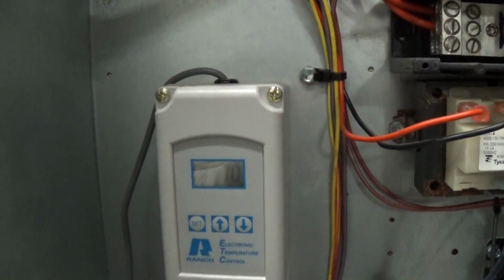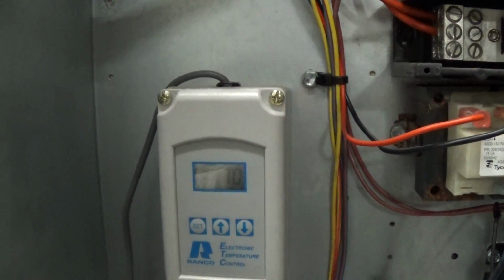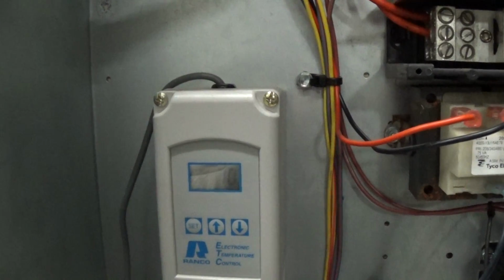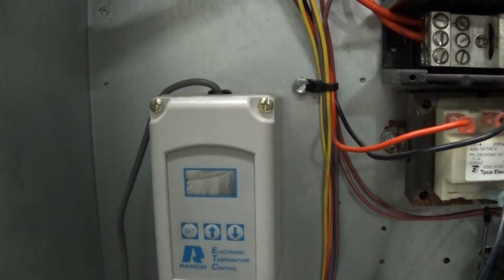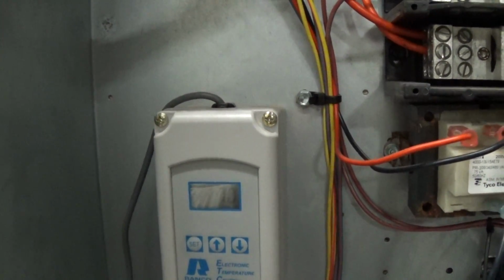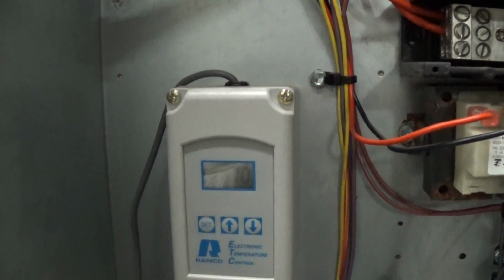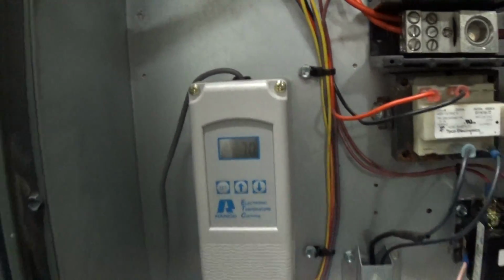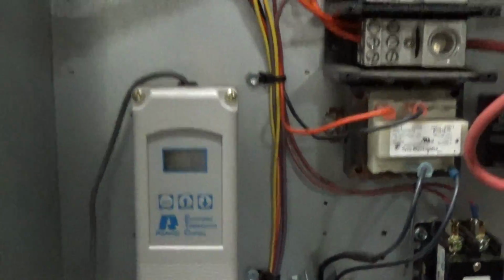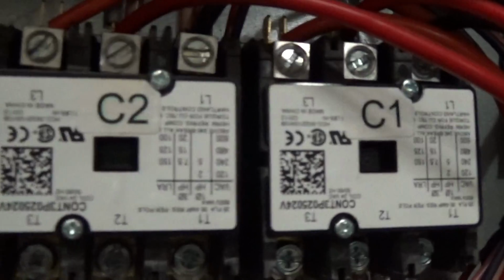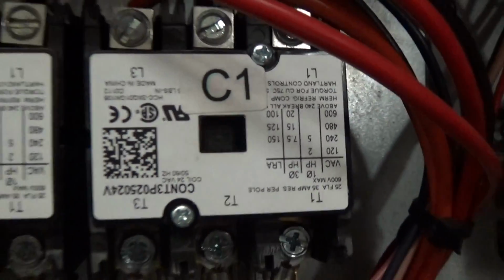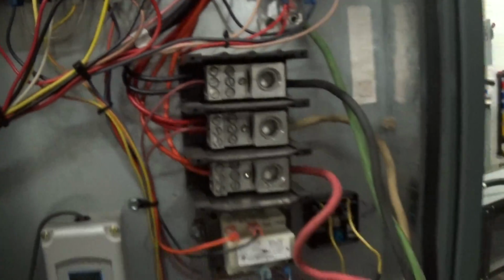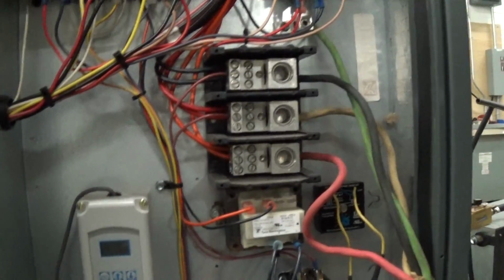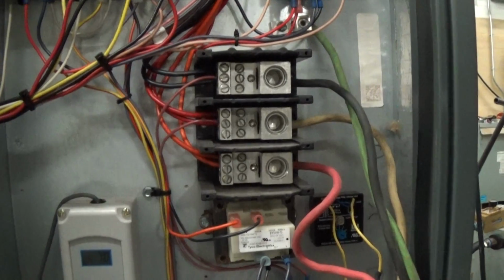And then over a period of time, you can alternate between circuit 1 and circuit 2 as to which has the slightly higher differential, just because one compressor will be working more often than the other. But a real simple controller. This unit here, and by the way, we know both compressors are on because you can see that the contactors are both clicked in. Now this unit here is a 208 230 volt 3-phase unit.